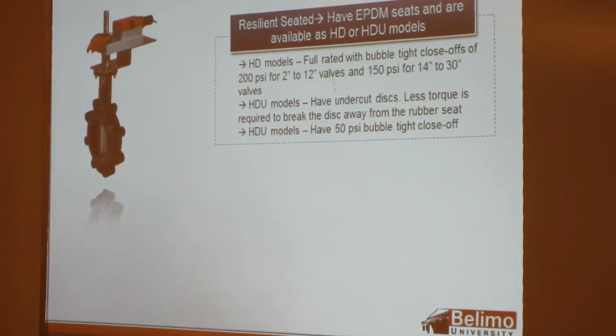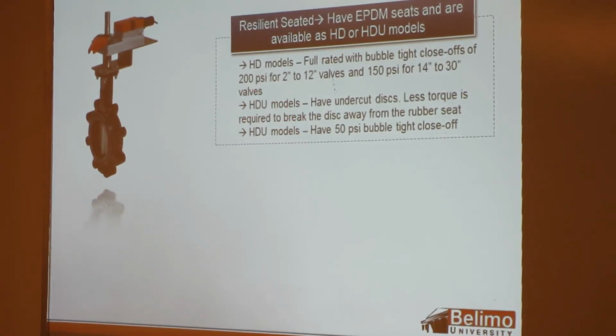We have a couple different types of butterfly valves. We have our resilient seated that have EPDM rubber linings, available in HD and HDU models. The U means that it has an undercut disc, lower close-off rating on those. You can see the HD model is a 200 PSI close-off for 2 to 12 inch, 150 for 14 to 30 inch, whereas the HDU models are all 50 PSI close-off. And what that undercut model does is require less torque to break away from the seat, which can certainly be an issue. So if you really need the high close-off pressure, then you're going to want to go with HD models.